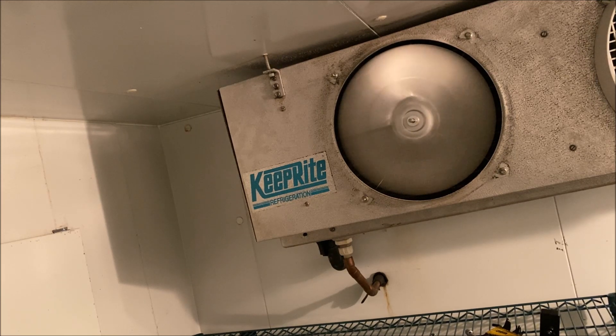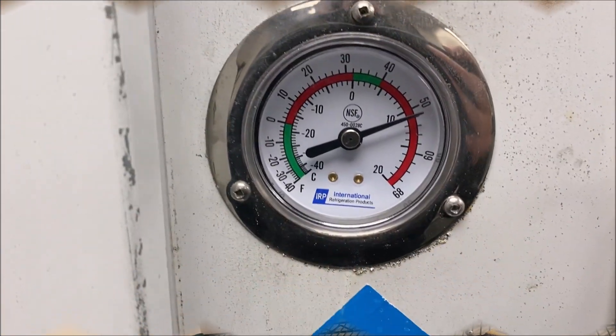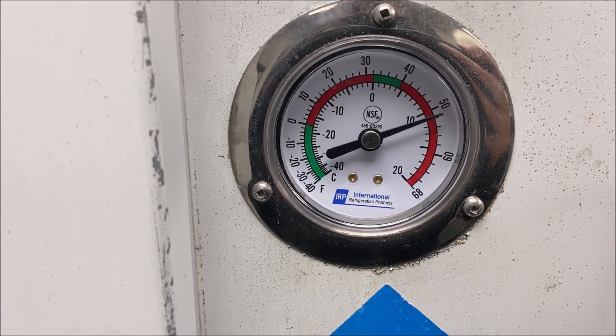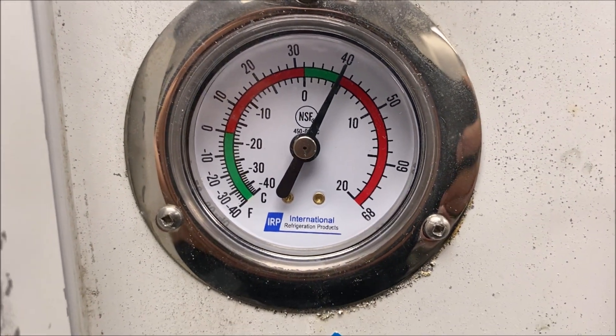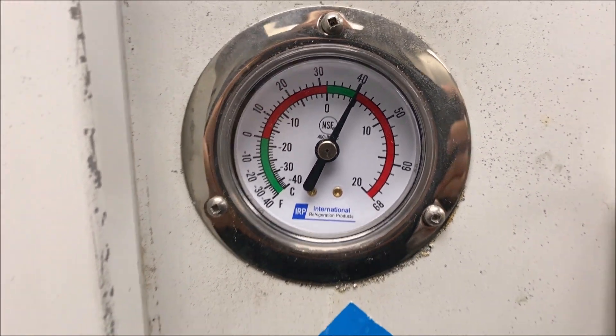Fan is running — that's good news. Box temp is coming down nicely. One degree per minute is my target right now, and we're at 40 degrees. We cycled off — we need a thermostat adjustment, but we're all good here.